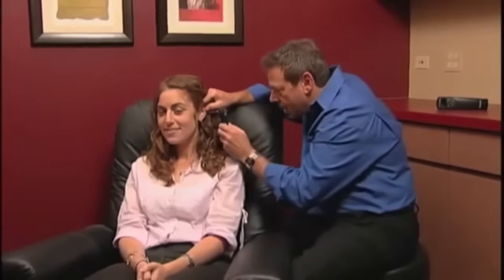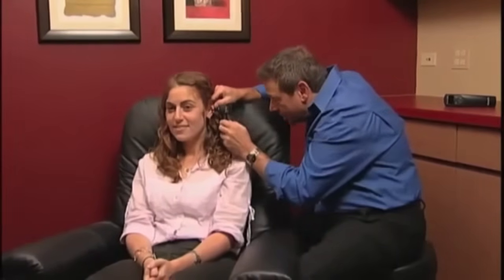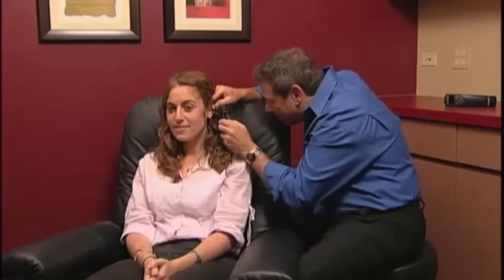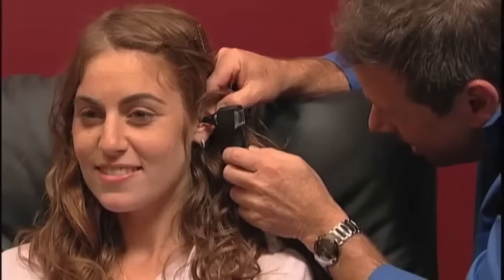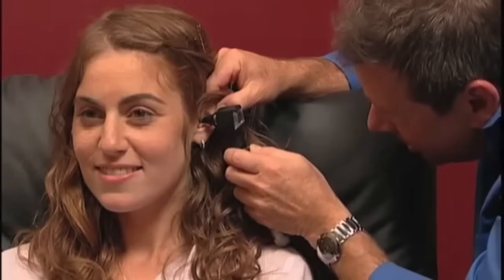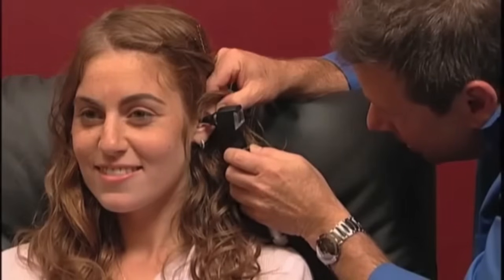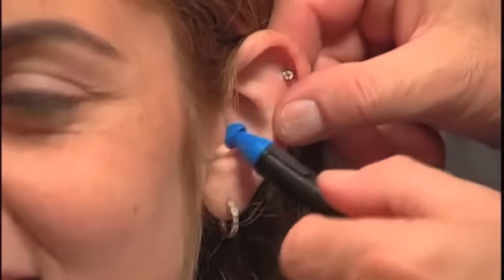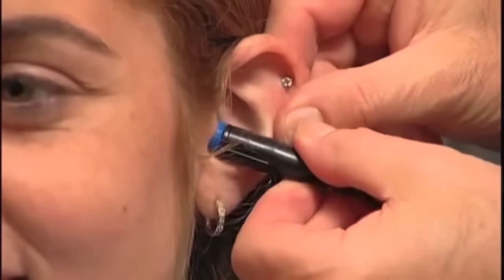Whenever practical, the next step should be to do an otoscopic or visual examination of the patient's ear canals. Excessive cerumen or vernix in the ear canals may interfere with the test and give invalid or incomplete results. Patients with excessive cerumen or foreign matter in the ear canals should be referred to an audiologist or physician for removal of the blockage prior to testing. If the canals are clear, place the patient in a position that permits easy access to the ear and allows the Ero Scan Pro to be held steady while testing is in progress.